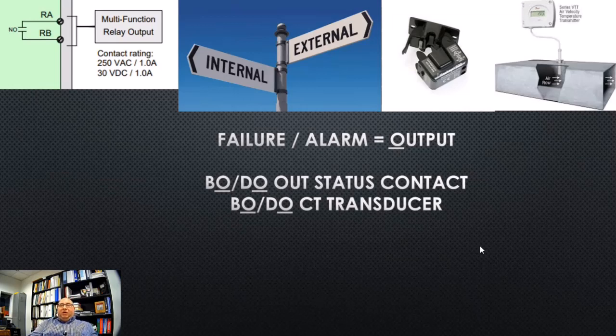Like I said, we want to also include some sort of failure and alarm system. A failure and alarm would be an output on the drive. It's going to be a discrete or binary output going into a BMS system or an alarm panel. And we could continue to use, and I highly recommend using, the relay output on the drive. We will know that the drive failed, all right, internally. And if we also installed, okay, for status inputs, a CT status, also known as a Hawkeye, around the wire, or a velocity sensor, we could also generate a second alarm when we don't have a proof of movement of the motor, okay? Because you might get an alarm on a motor on the VFD drive, but it still might run. It may be like a soft alert versus a hard failure alarm. So by doing it this way, you get a relay output from the drive, and you also get a status that will not coincide with the run command, and then therefore you'll have a better alarm system built into your BMS.